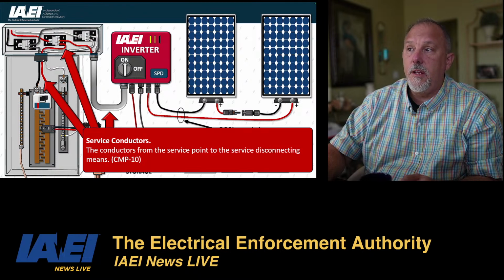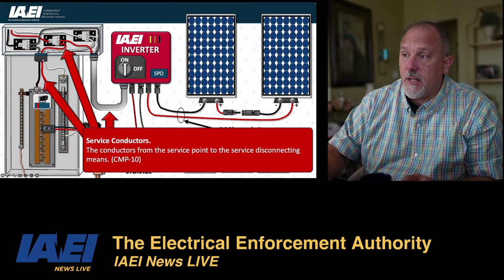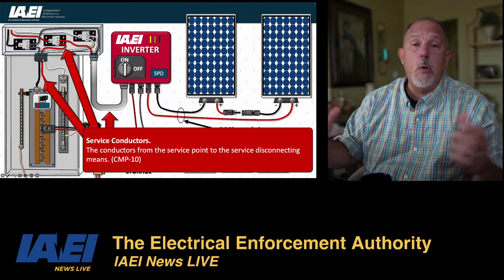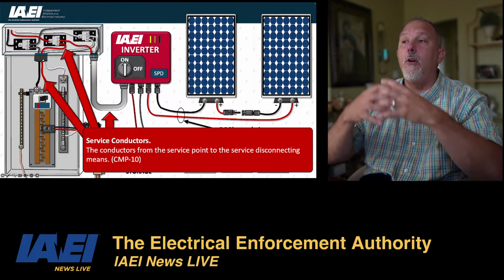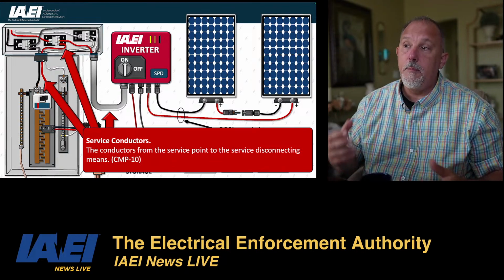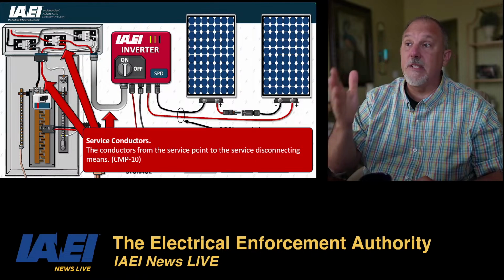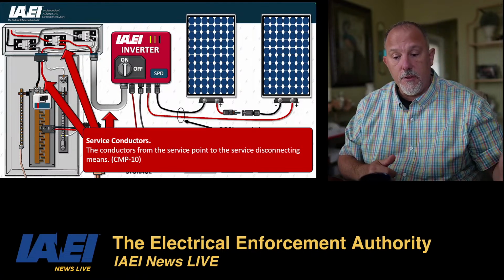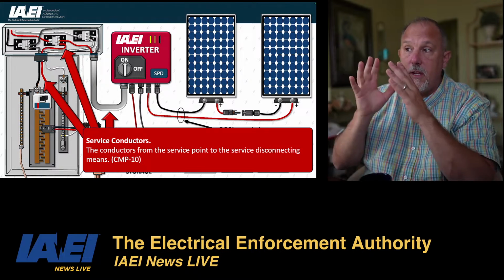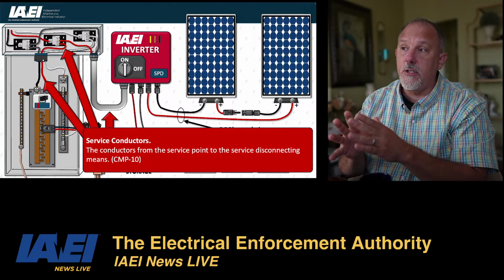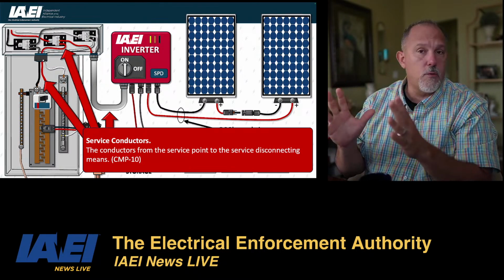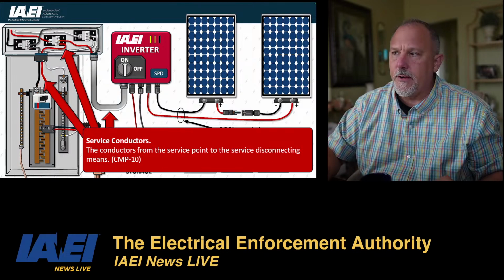In 230, once you call these service conductors, then you pull in Article 230 and all of the provisions of 230, because they are service conductors, service entrance conductors. You have to follow the rules in Article 230 to physically protect those conductors and follow all the different rules for bonding, all that good stuff. All right.